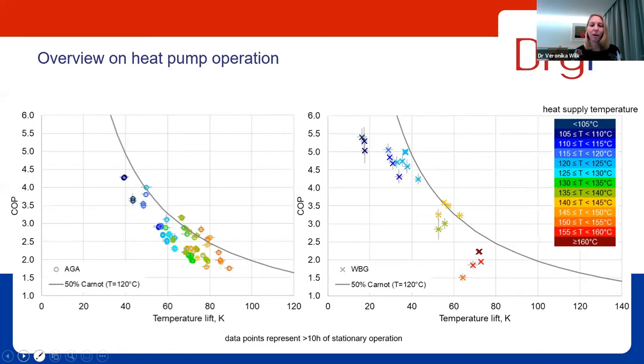And in those two diagrams, the COP is presented over the temperature lift, and that's the temperature difference between the heat sink and the heat source. So this is basically a measure for the amount of work that is provided by the compressor. On the left, we have values for the Agrana demonstrator, and on the right, values for the Wienerberger installation. And you also see a color code that represents the heat supply temperature, starting with dark blue. Those are the low temperatures, ranging over green to orange to red for the high temperatures.